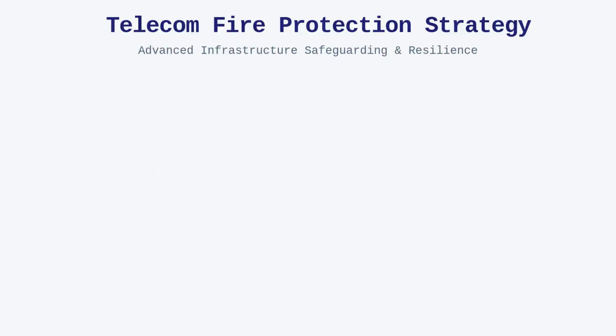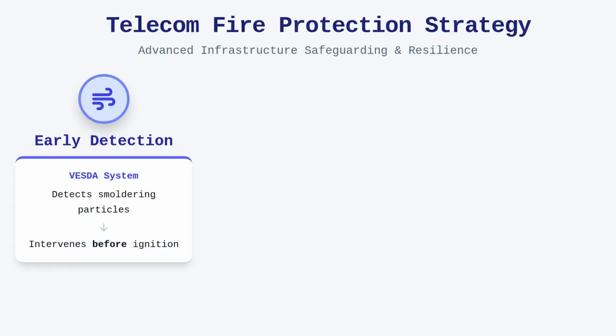Fire protection in telecom environments requires a departure from traditional water-based sprinkler systems to prevent collateral damage to electronic components. We utilize very early smoke detection apparatus, or VESDA, for its ability to detect the combustion particles of smoldering materials long before a traditional smoke detector would activate. This allows for early intervention, often before a fire has even fully ignited, protecting the mission-critical assets from both direct heat and subsequent cleanup efforts.